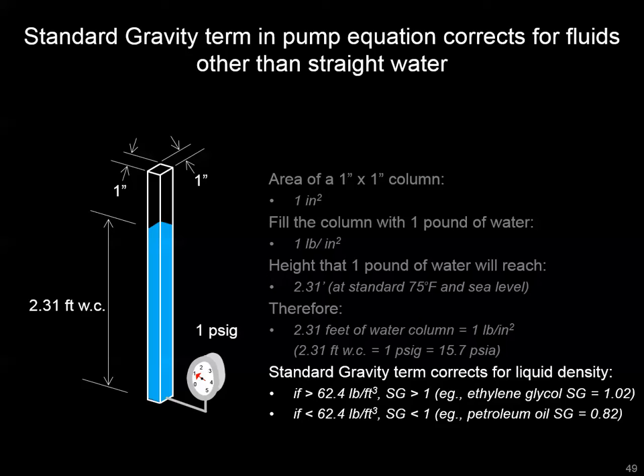The pump equation also has an SG, or specific gravity, term. This accounts for how much the density of the fluid in your system differs from ideal water. Water has an SG of 1. Ethylene glycol has a very slightly different SG — probably not enough to cause a meaningful change in your pump energy equation, but good to note as you vary from typical HVAC hydronic conditions.